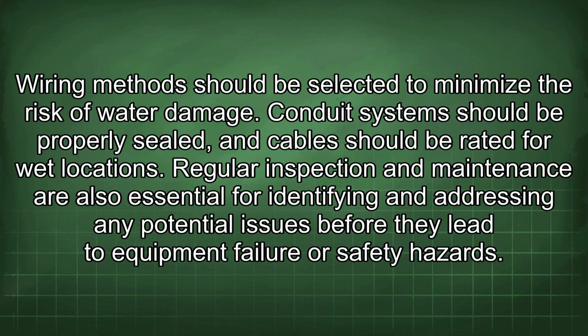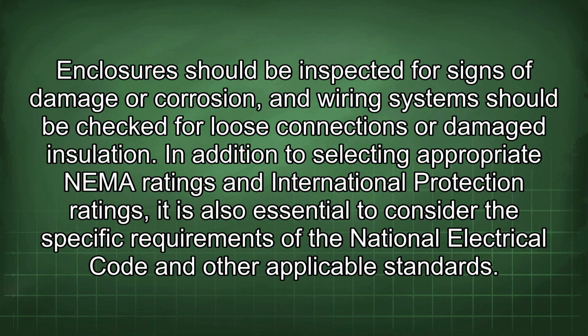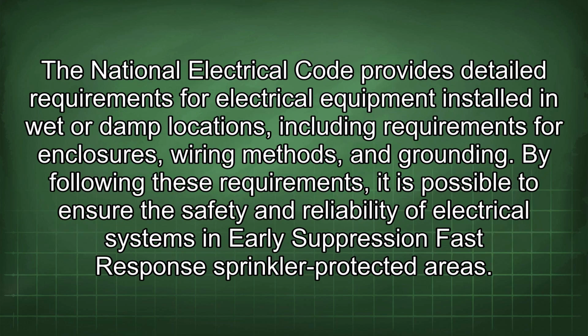Regular inspection and maintenance are also essential for identifying and addressing any potential issues before they lead to equipment failure or safety hazards. Enclosures should be inspected for signs of damage or corrosion, and wiring systems should be checked for loose connections or damaged insulation. In addition to selecting appropriate NEMA ratings and international protection ratings, it is also essential to consider the specific requirements of the National Electrical Code and other applicable standards. The National Electrical Code provides detailed requirements for electrical equipment installed in wet or damp locations, including requirements for enclosures, wiring methods, and grounding. By following these requirements, it is possible to ensure the safety and reliability of electrical systems in early suppression fast response sprinkler protected areas.